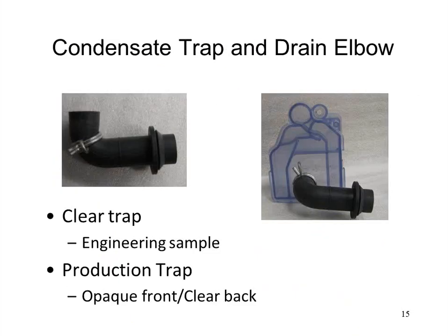The condensate trap is not clear. Originally it was supposed to be clear, and that was so we can see if something was clogged in there, which is obviously a great service technician troubleshooting feature. However, homeowners complained that they didn't like seeing water and slime and things sitting in there. So we got rid of that idea. And now the front of it is opaque, meaning it's fully colored, either black or white, depending on which version of the furnace you have. And the back of it is still clear. So a technician could take the condensate trap off, the collector box off, see the back side, and then know if it's plugged or not plugged. The front of it's not visible anymore.